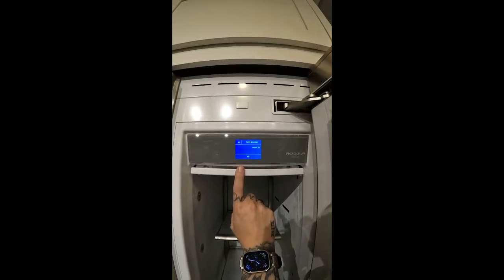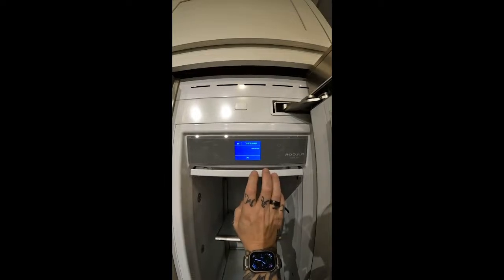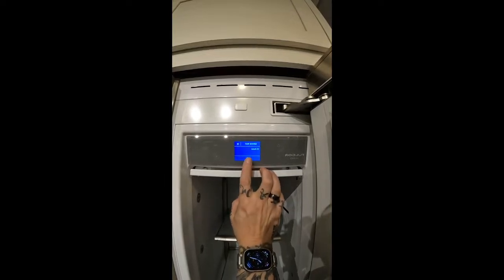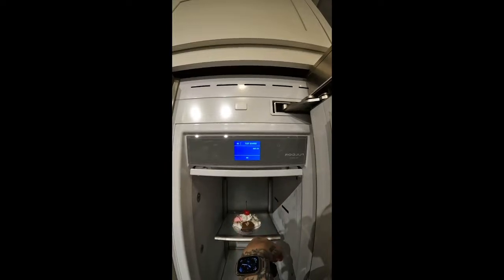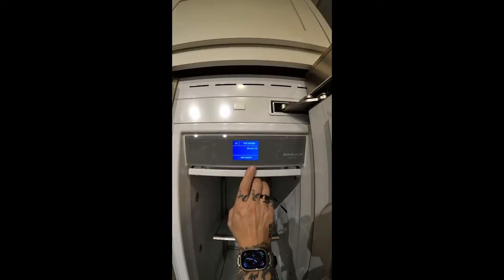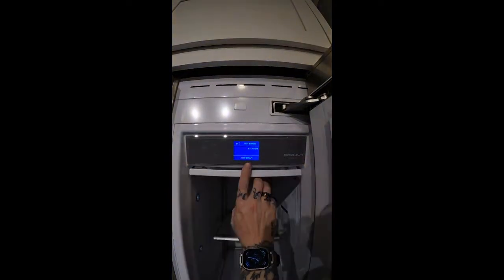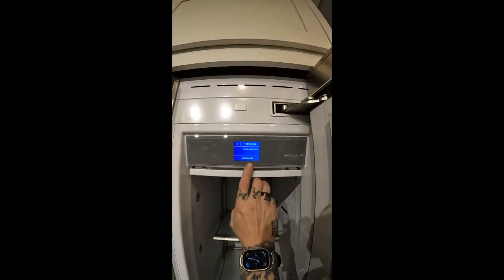So you're going to be pushing the button OK a little bit more than you necessarily want to. But V3 heater, this is something that we would use. V3 is a freezer column, and this is the defrost heater. You would physically check for voltage to your heater, or you can check your heater for continuity. You can actually hear it start to pop right now. It's starting to get hot inside of there. V3 fan, fresh food fan, your freezer fan. You might be able to hear that ramp up. Like I said, there are multiple legacy features in here that you're going to flow through, but fans, heaters, and compressors are going to be your big ones that you're actually going to go into service mode for.